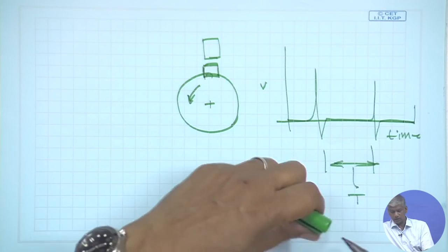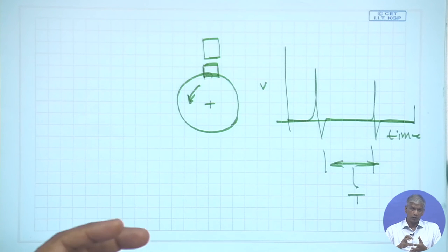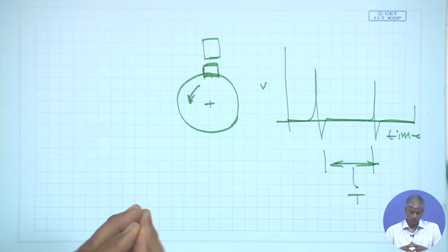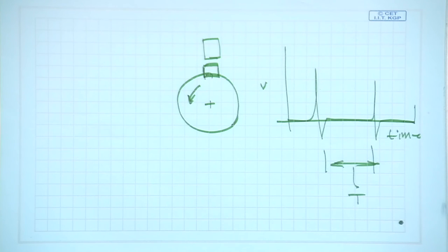Of course, nowadays we use optical encoders even to see the fluctuation of rotational speed even in one rotation, and a lot of diagnostics could be done by observing the change in the rotational speed even in one rotation. But in noise control, many times I need to know the machinery source noise characteristics which are related to the rotational speed. If you talk about, say, a blower with maybe 40 vanes, the vane pass frequency would be 40 times the rotational speed. So I need to measure the rotational speed, and we can use this simple key phaser to do that.